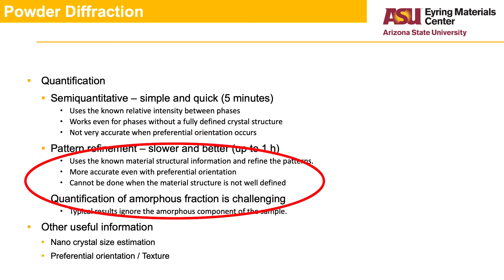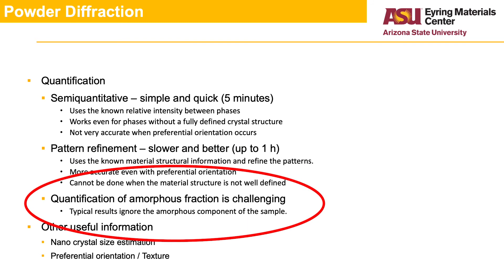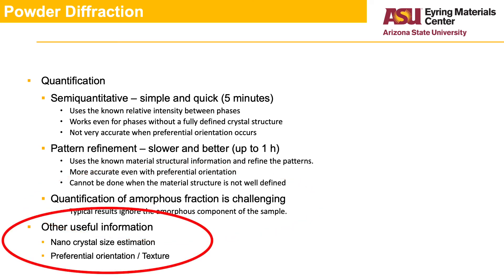Another issue that can affect the results is the presence of an amorphous component in the sample, which can be challenging to quantify. Most analyses assume the sample is fully crystalline. Powder diffraction can also provide additional information about the crystallite size for nanocrystalline materials, as well as information on preferential orientation, also referred to as texture, which is often an important factor to consider in metallurgy, for example.